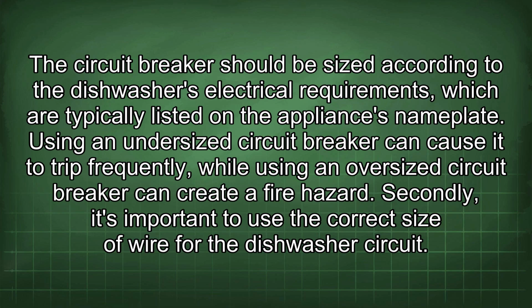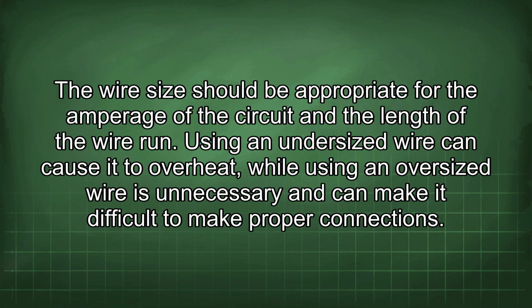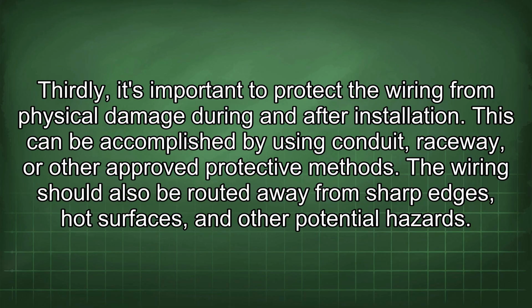Secondly, it's important to use the correct size of wire for the dishwasher circuit. The wire size should be appropriate for the amperage of the circuit and the length of the wire run. Using an undersized wire can cause it to overheat, while using an oversized wire is unnecessary and can make it difficult to make proper connections. Thirdly, it's important to protect the wiring from physical damage during and after installation. This can be accomplished by using conduit, raceway, or other approved protective methods. The wiring should also be routed away from sharp edges, hot surfaces, and other potential hazards.